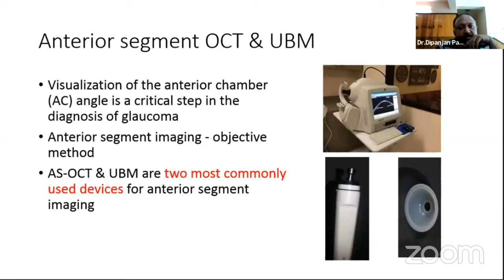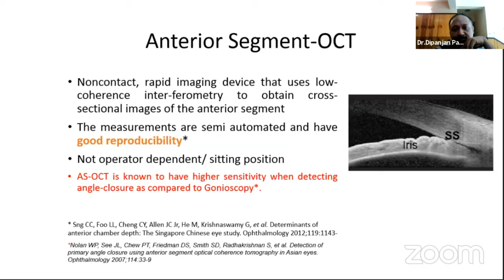Anterior segment OCT and UBM are the two most commonly used devices for anterior segment imaging. Anterior segment OCT is a non-contact rapid imaging device that uses low coherence interferometry to obtain cross-sectional images. The measurements are semi-automatic and have good reproducibility, it is not operator dependent, and it can easily be done in a sitting position. It is known to have higher sensitivity when detecting angle closure compared to gonioscopy. And when we go through the different ages of anterior segment OCT, from time domain to spectral domain to now available swept source OCTs, the scan speed has increased from 200 per second to 20,000 per second.